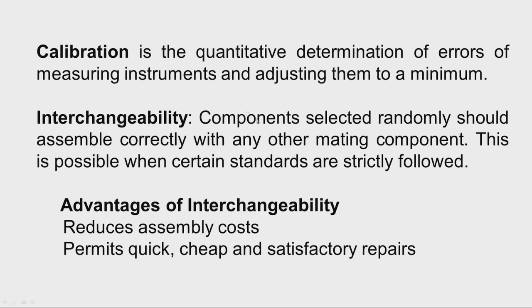Calibration is the quantitative determination of errors of measuring instruments and adjusting them to a minimum. All instruments undergo wear due to continuous usage, and due to wear there will be an error. So at regular intervals, we have to compare the accuracy of these instruments with equipment available at the standards room of the plant, and whatever error is found should be recorded on the instrument. This process is known as calibration.